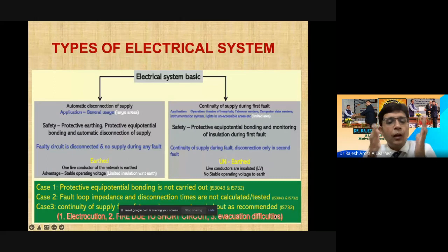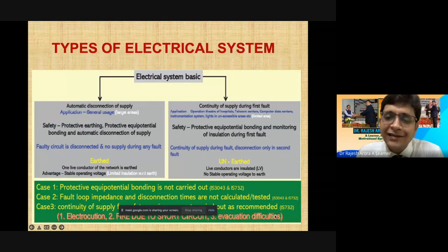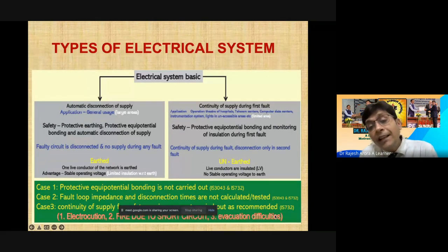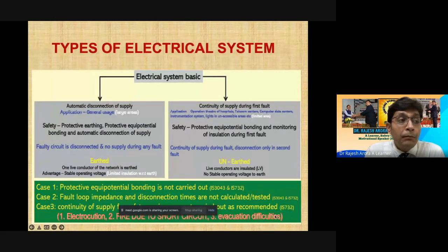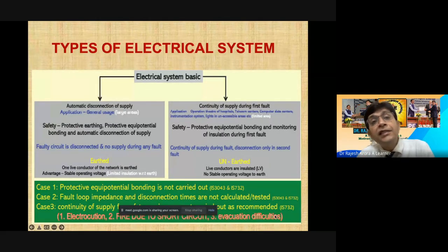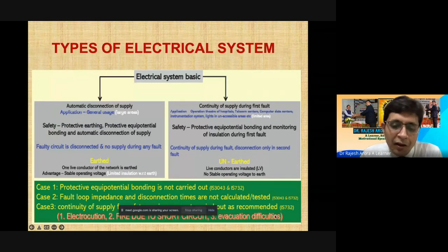When your system is grounded, that is called an earthed system. When it is not grounded, that becomes unearthed. And in the absence of earth, there will be an unearthed system. But there are areas where you have to maintain that continuity of supply, specifically in some medical areas, some hospitals, some specific industry where you can't bear with any fault. But with all these systems, you have to be very much careful.